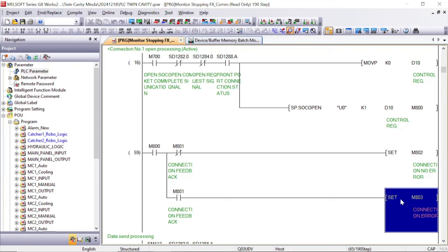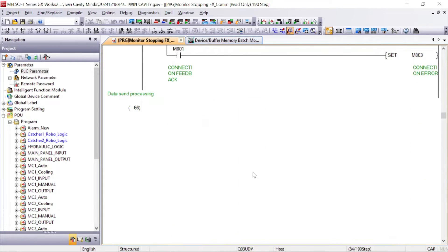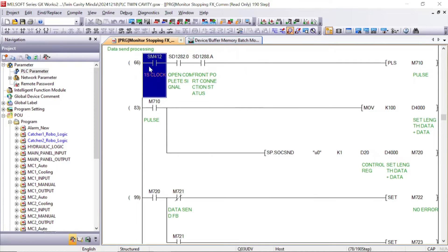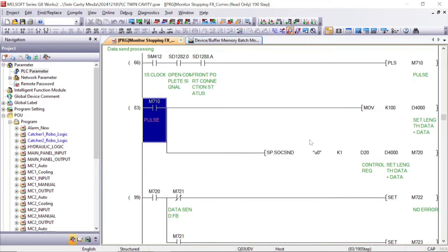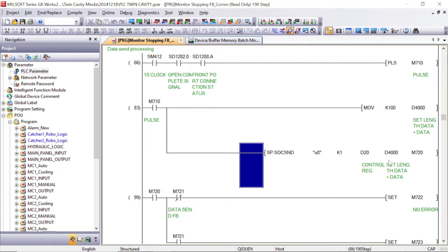This program is for data send processing. To send data, we have written the socket send instruction. D4000 — we are going to send 100 registers of data to the FX5U. That's why I have moved K100 into D4000, so from D4000 to D4100, data will move to the FX5U PLC.